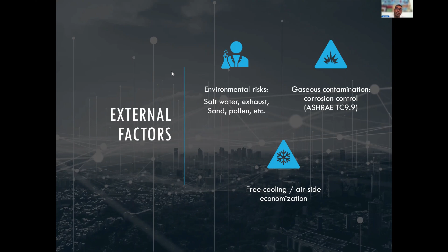And another thing to consider is free cooling. In other words, air side economization. And that's just allowing fresh air into the facility. That's a good thing. We'll talk about the WELL building standard in a few minutes, and we'll talk about why getting fresh air into the space is good, but it must be conditioned. Otherwise, you're going to be allowing a lot of particulates in here, pollen, leaves, bird feathers. So we'll talk about filtration strategies for that.